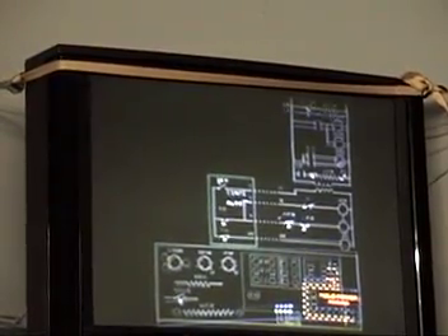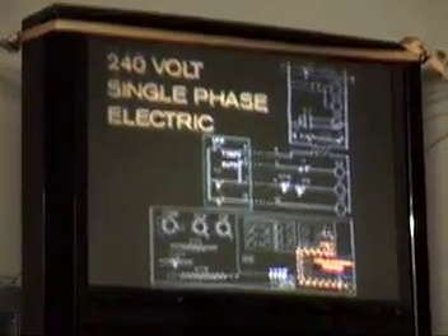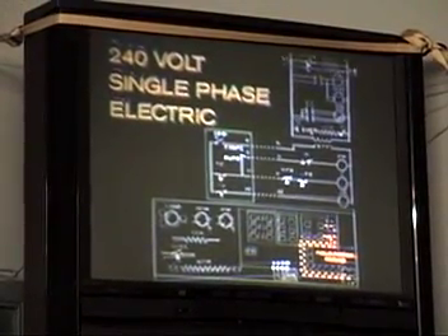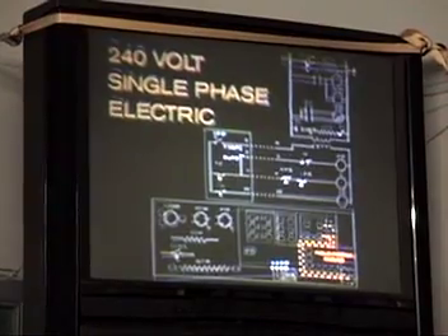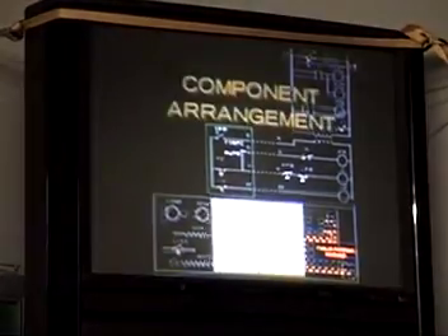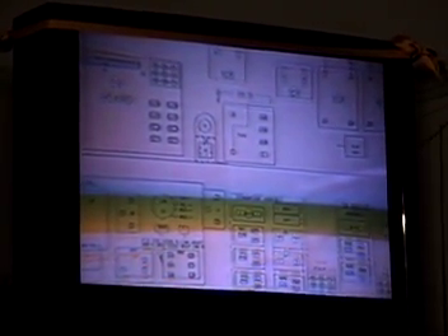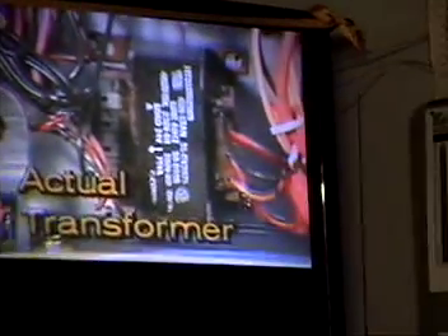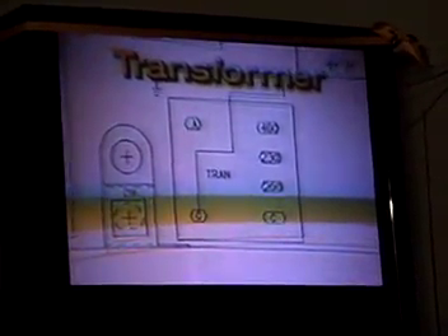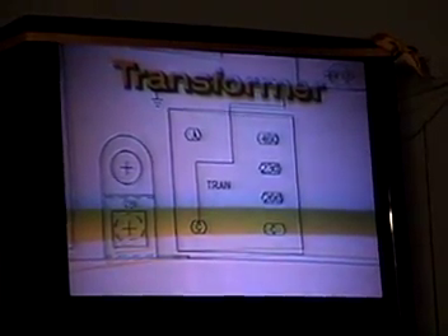In this part of the program, we'll cover a typical electrical arrangement of a 240-volt single-phase package unit with electric heat. The wiring diagram is composed of 3 major sections. The first section, the component arrangement, shows the physical location of the components as they're grouped in the unit. This is a physical location aid and corresponds to approximate locations of unit components. For instance, the transformer shown here on the unit is in the same location relative to other components as it appears on the physical location section of the wiring diagram. Component arrangement may vary between different models within a unit family.